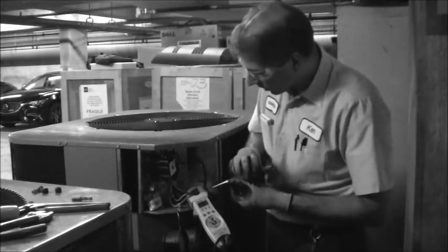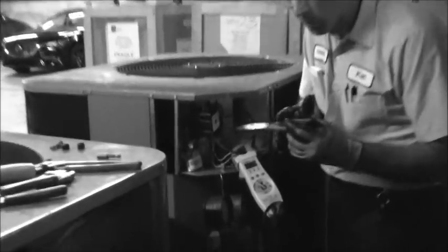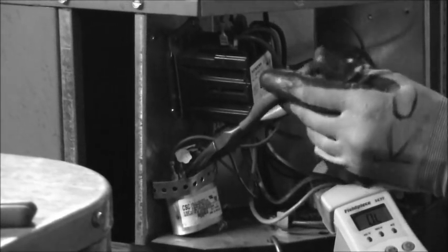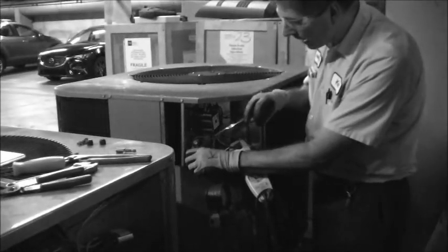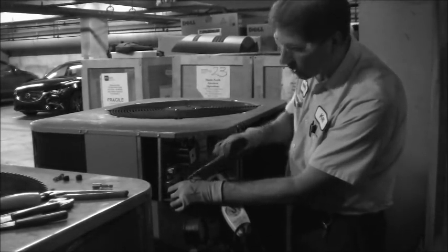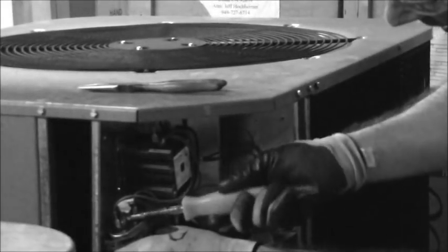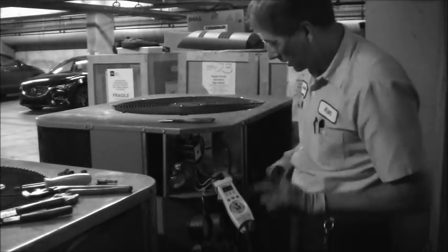So I shorted this. The electricity is off. I'm just going to take my needle nose pliers while holding the insulated handle, and I'm going to touch against the 2 leads of the capacitor like this. If there was any residual voltage stored in this capacitor, that voltage would be dissipated by doing a direct short. So that's how you do that. You just take it and short it out like that. You can also use a screwdriver like this and just touch it like that, and just make sure that you've got good clean metal and you're shorting that out. Okay, next.